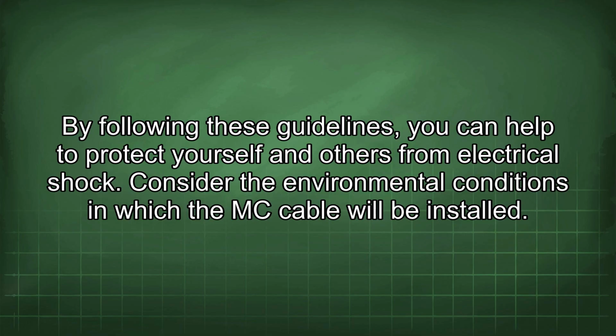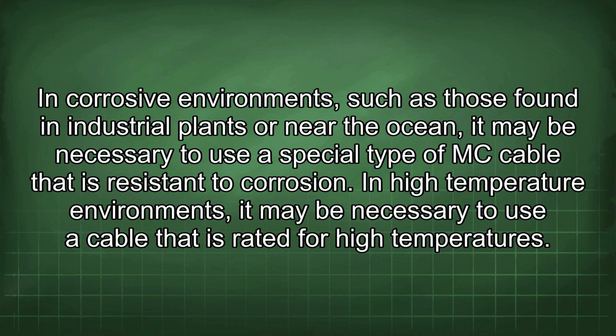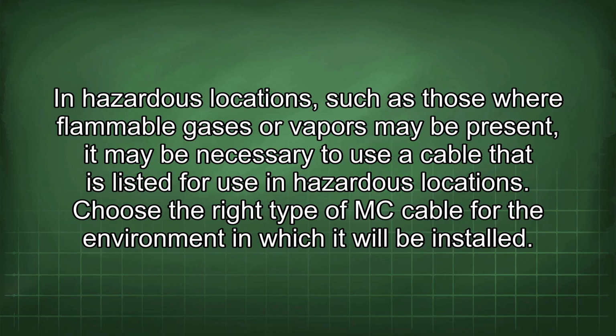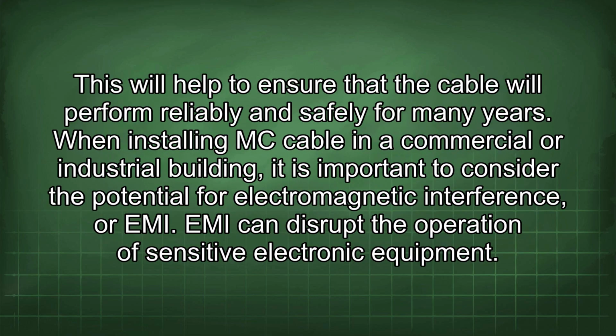Consider the environmental conditions in which the MC cable will be installed. In corrosive environments, such as those found in industrial plants or near the ocean, it may be necessary to use a special type of MC cable that is resistant to corrosion. In high-temperature environments, it may be necessary to use a cable that is rated for high temperatures. In hazardous locations, such as those where flammable gases or vapors may be present, it may be necessary to use a cable that is listed for use in hazardous locations. Choose the right type of MC cable for the environment in which it will be installed. This will help to ensure that the cable will perform reliably and safely for many years.